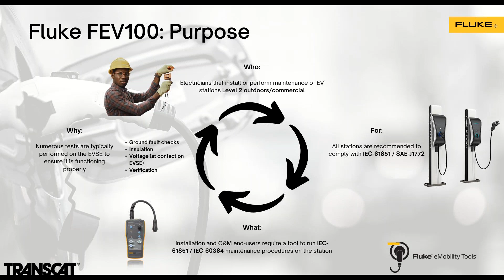This unit, in conjunction with either a digital multimeter or a scope meter, is going to allow you to do several functions on the charging station. You're going to be able to check if it's grounded correctly, if the ground fault and GFCIs work. You can do insulation tests as well, and validate that the voltage and control signaling are working correctly. All of this can be done through the FEV 100.